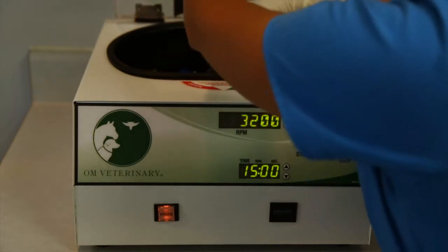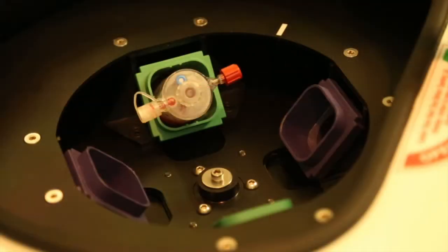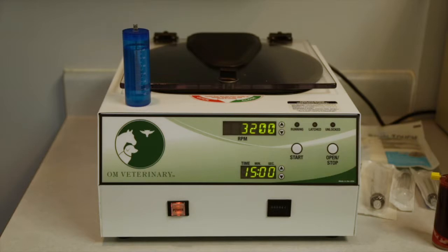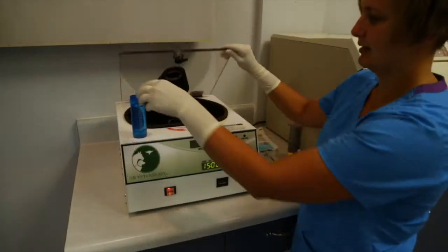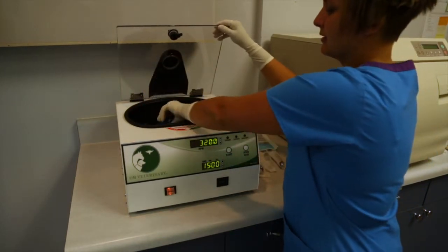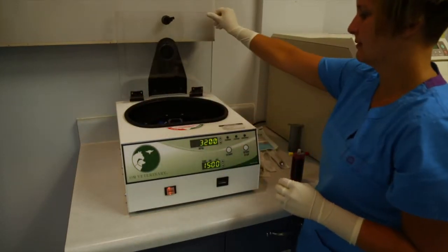Make sure to load the device with the ports placed horizontal, facing left and right, and not vertical. The green centrifuge buckets must be used with Pro-Stride. It is critical that the centrifuge is balanced. This can be achieved by using the blue 60 ml counterbalance positioned in the green centrifuge bucket opposite the device. Water may be added to this counterbalance to adjust for any variance in the weight of the blood volume placed in the first device. Alternatively, if a second kit is being processed, both devices will allow for proper balance.